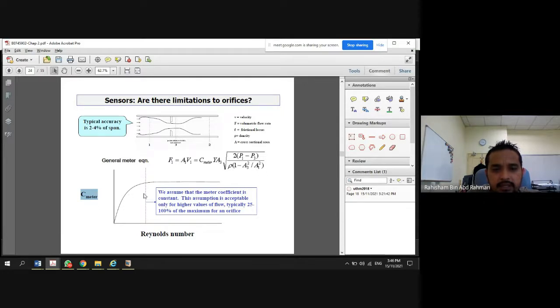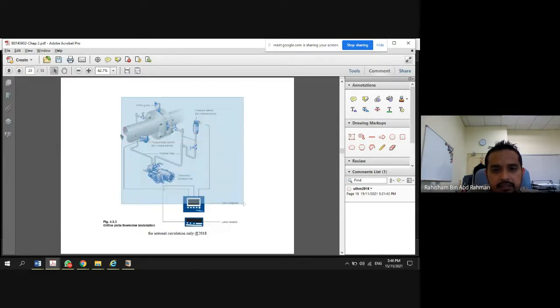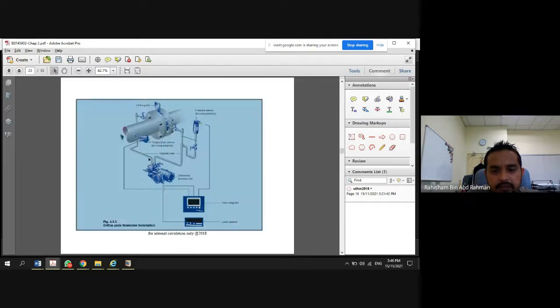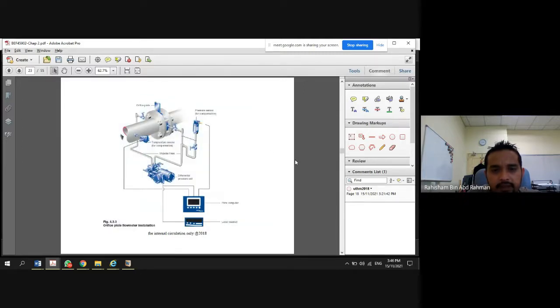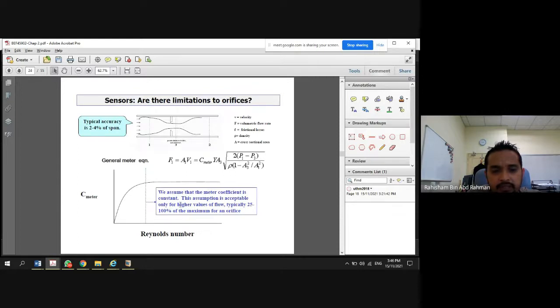Okay, kita ada gauge tadi kan. Okay, this one. Kita ada gauge ni and kita ada meter for monitoring, and then we assume the constant for meter at this point. We assume that the meter coefficient is constant, and this assumption is acceptable for very high value of flow. Okay, kalau flow rendah mungkin tak valid. And that means the assumption made is only valid for higher values of flow. Okay, higher value of flow, typically 25 to 100% of the maximum for the orifice plate.